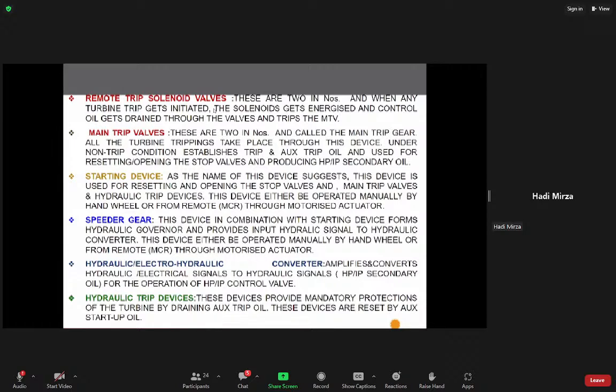Basically, it opens the port from control oil to trip. It changes the port of the valve from control oil to trip oil to control oil to drain. When the unit trips, it means the port from RTS is changed from control oil to drain. Basically, this happens in RTS. Main trip valve.